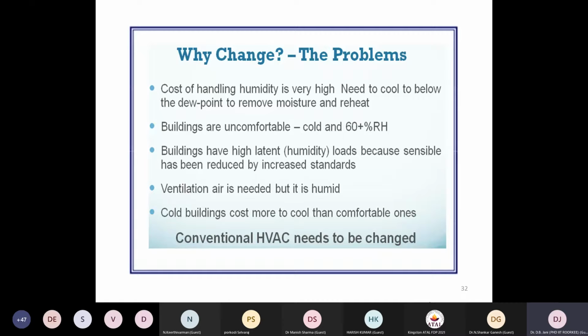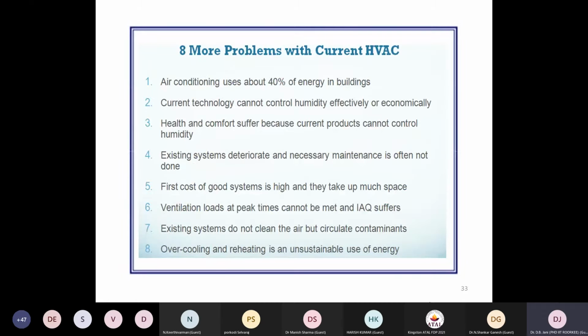In humid areas, a different design and suitability of the system should be considered. In general, air conditioning devices consume almost 40% of the total building energy. Conventionally used HVAC, typically with vapor compression, cannot control humidity effectively. Why not effectively? Because when the humidity load is high, you might have to cool the air too much to reach the dew point. And whenever you reach the dew point, the compressor work has to increase and the evaporator temperature has to be drastically reduced. That will increase the energy consumption and reduce the COP of the system.